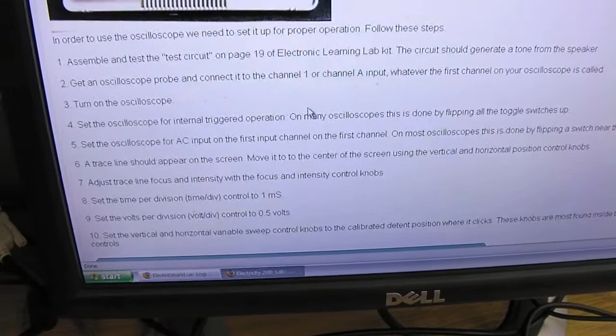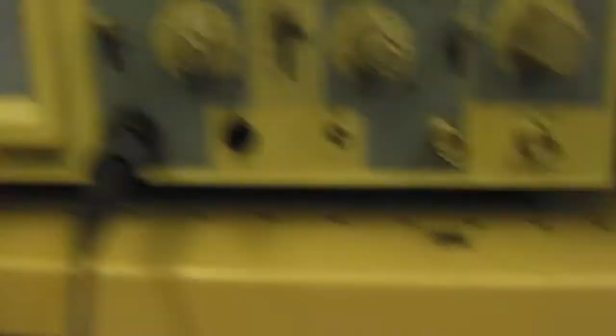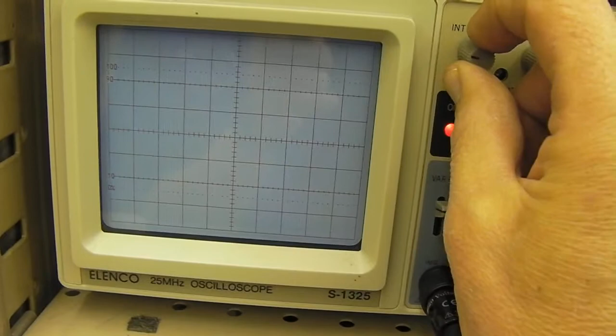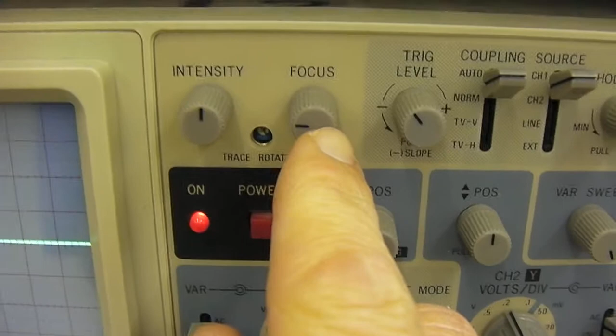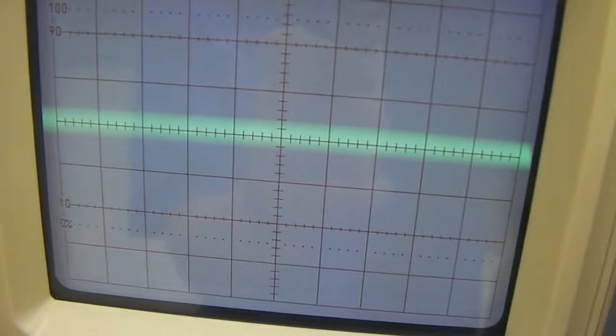And then it tells us here that we want to adjust the trace line focus and intensity. So what's that? Well, you got a control here for brightness or intensity. So you can turn it up bright or dim. That's that one right there. It says intensity. And then there's also one for focus. And what focus does, if you have it out of focus, well, it's just all blurry. So you want a nice sharp line so you can look at. So you just adjust that so it gets a nice sharp line like that.